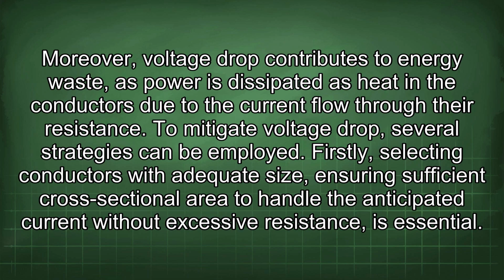Moreover, voltage drop contributes to energy waste, as power is dissipated as heat in the conductors due to the current flow through the resistance. To mitigate voltage drop, several strategies can be employed. Firstly, selecting conductors with adequate size, ensuring sufficient cross-sectional area to handle the anticipated current without excessive resistance, is essential.